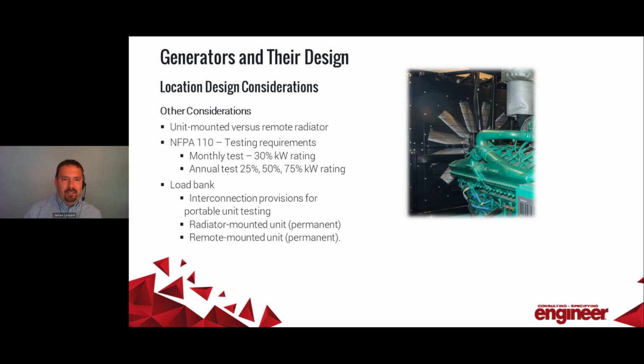Other considerations: do you have a unit mounted radiator? Is it mounted, strapped right on the front of the engine chassis, or do you have a remote radiator that's up on the building? Do you have to pipe coolant system up through the building, up onto the roof? Something else to coordinate. NFPA 110 dictates very specific testing requirements for your generator system. This requirement falls on the facility, of course.